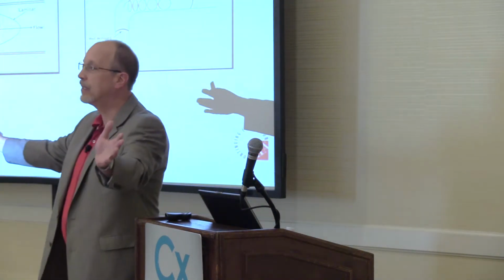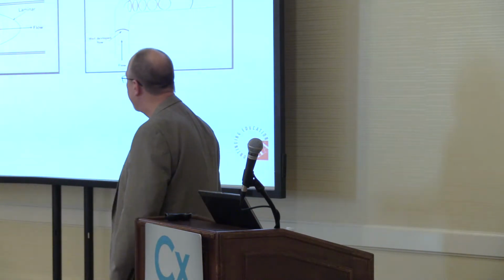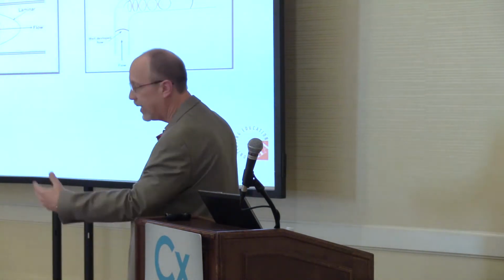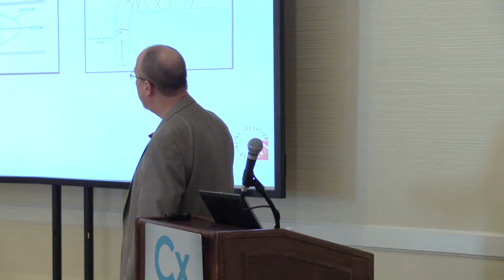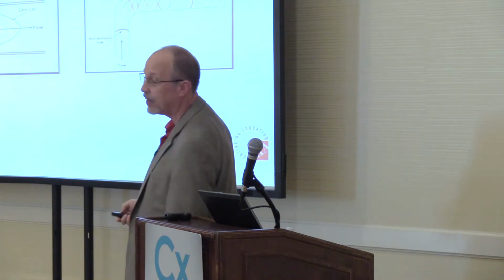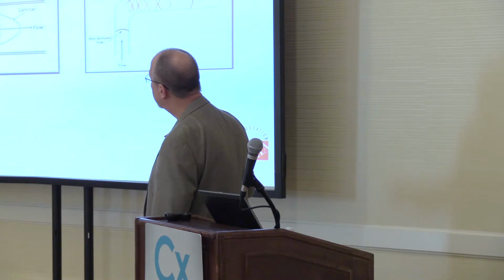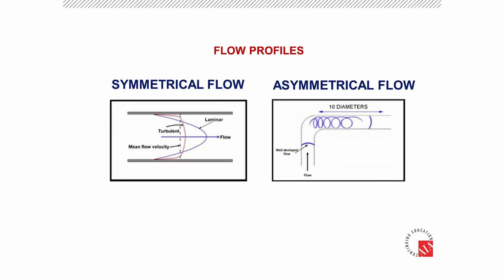It's much like a motorboat going down the river and the wake cast out to the side. Well, gravity and friction grab hold of the flow, depending on the type of flow and type of liquid there. It'll be slower at the pipe wall and fastest at the center. So what we want is the flow fastest at the center of the pipe. We call that a symmetrical flow profile. Now, regardless of whether it's turbulent, the shape of the parabola will change based upon the flow rate, and we define that with what's called a Reynolds number. We don't care about that. We care about, if we were to draw a center line down this pipe, the top half of pipe equals the bottom half of pipe.